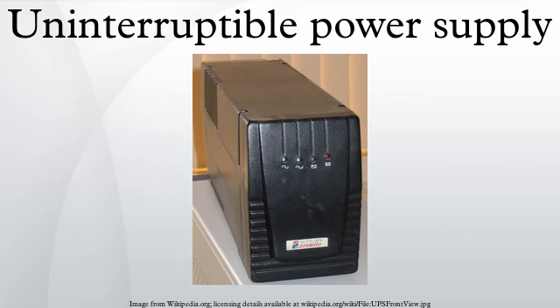DC power. A UPS designed for powering DC equipment is very similar to an online UPS, except that it does not need an output inverter. Also, if the UPS's battery voltage is matched with the voltage the device needs, the device's power supply will not be needed either. Since one or more power conversion steps are eliminated, this increases efficiency and runtime. Many systems used in telecommunications use an extra low-voltage common battery 48V DC power, because it has less restrictive safety regulations, such as being installed in conduit and junction boxes.